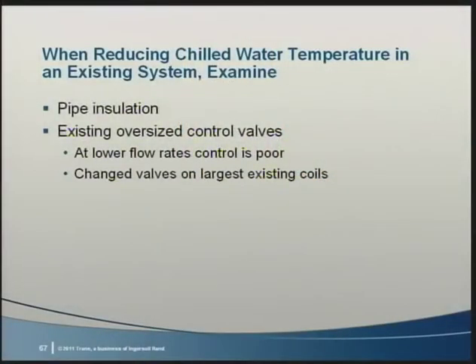The second issue was that some of the existing control valves were oversized. At the reduced flow rates, they would have been even more oversized, and the control would get worse, especially during part load conditions. So, they changed the valves out on the largest existing coils to get the biggest bang for the buck from a labor cost standpoint.